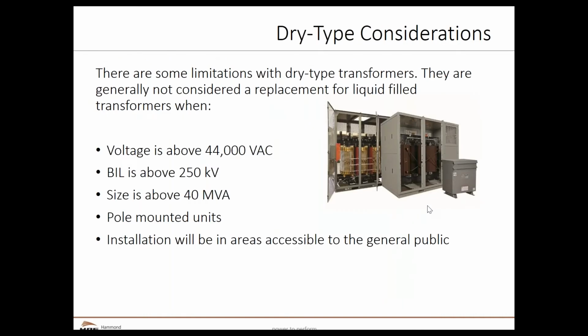So dry type transformers. Right now we're looking at applications below 44 kV. The BIL, which is the basic impulse level, the highest voltage level that a transformer can get hit by a not arc, we're looking at 250,000 volts, 250 kV. Typically, dry type transformers will be 40 MVA and below. That's a pretty big transformer. But when we start talking about 100 MVA main power transformers, typically high voltage units, those are really the domain of liquid filled transformers. Pole mounted units, we already addressed that earlier in our conversations.